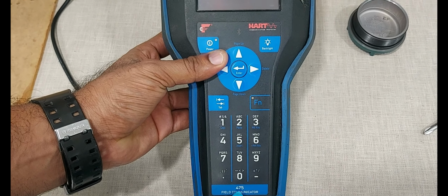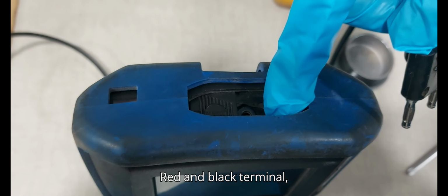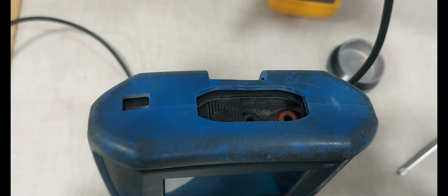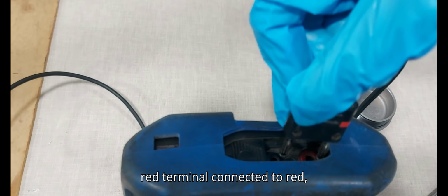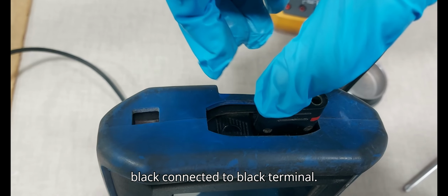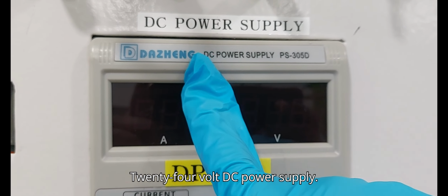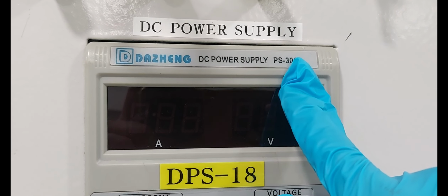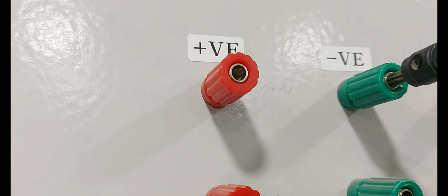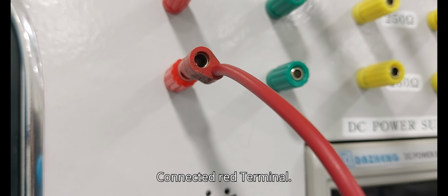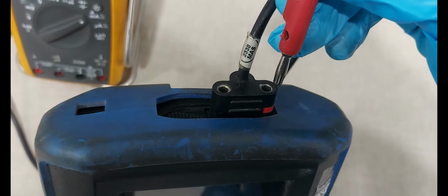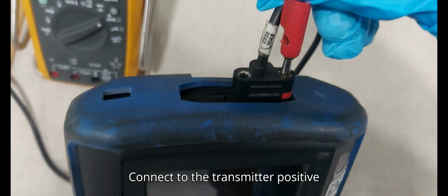Field communicator: red and black terminals. The red terminal is connected to red, and black is connected to the black terminal. 24 volt DC power supply, positive line: connect the red terminal to the transmitter positive terminal.